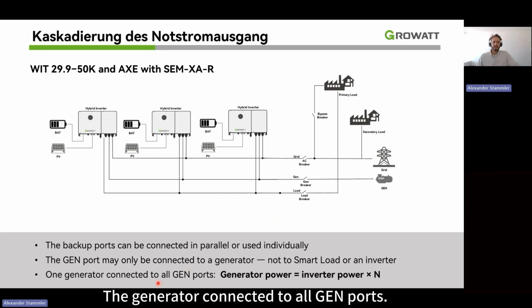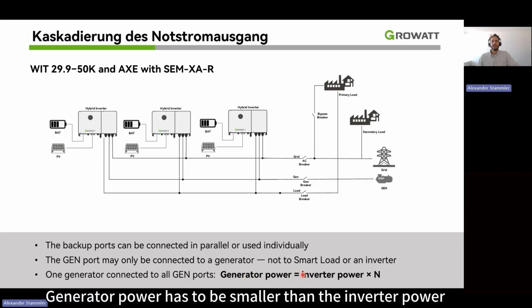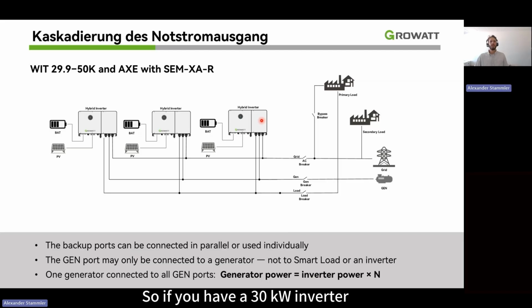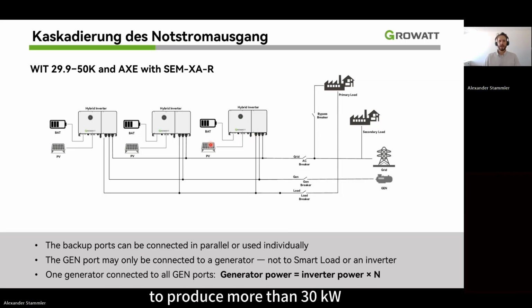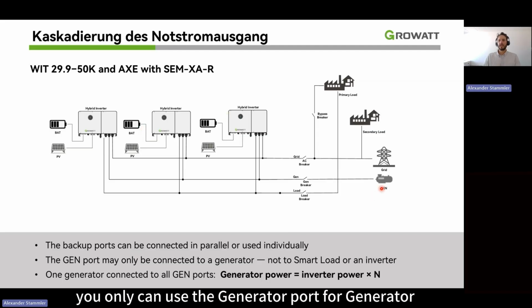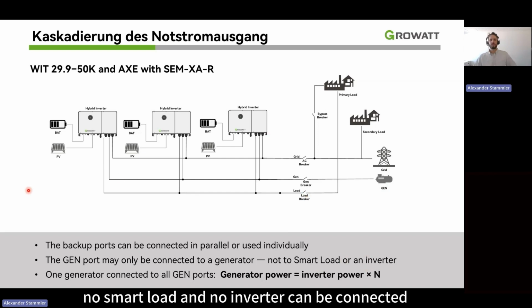The generator connected to all gen ports, generator power has to be smaller than the inverter power. So if you have a 30 kilowatt inverter, the generator is not supposed to be able to produce more than 30 kilowatt. Yeah. In parallel, you can only use the generator port for the generator. No smart load and no inverter can be connected.